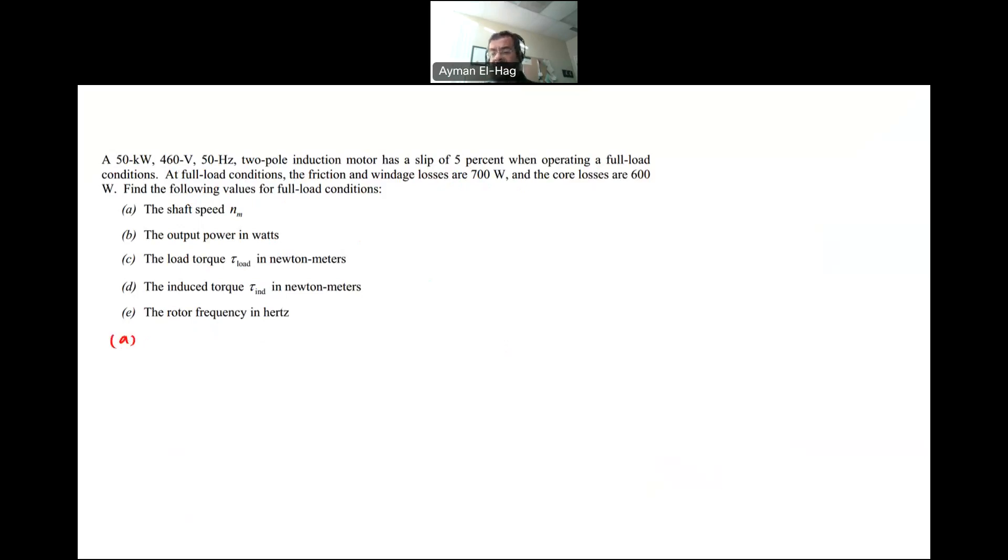To find the shaft speed, we have first to find the synchronous speed, which is the speed of rotation of the magnetic field, which is constant in the induction motor, and this we call it Nsynchronous, or sometimes we call it NS for short, is equal to 120 times the frequency, the electrical frequency, divided by the number of poles, and this is equal to 120, frequency is 50, divided by 2, and this will give me 3000 RPM.